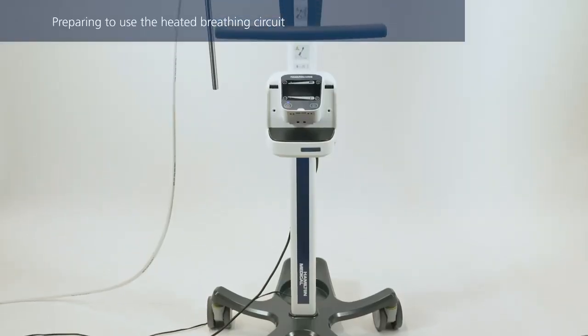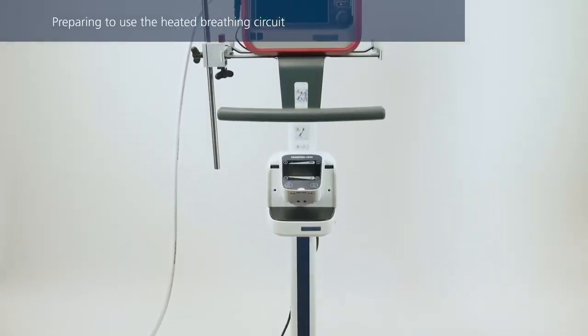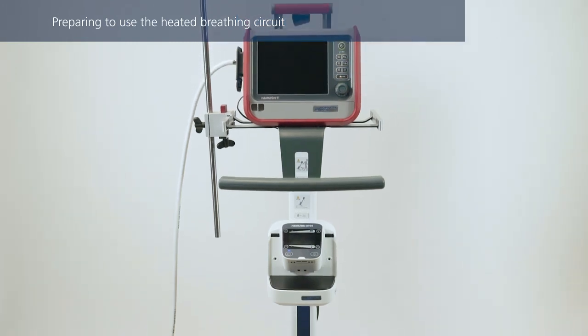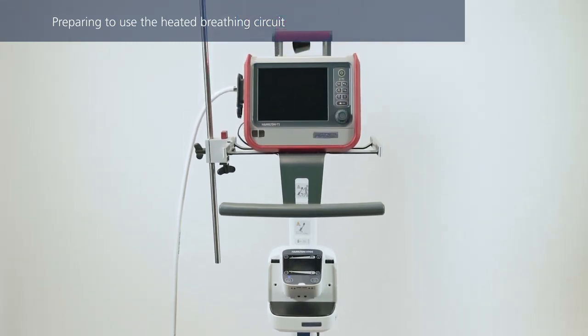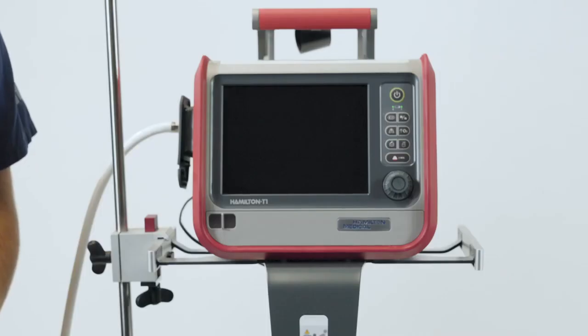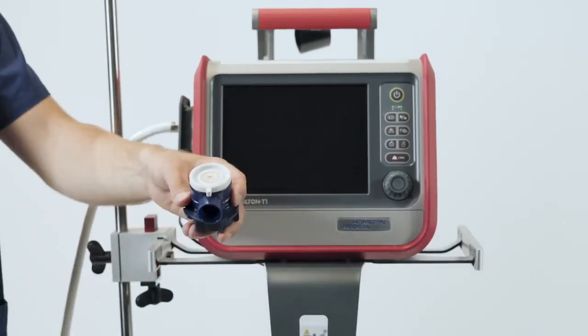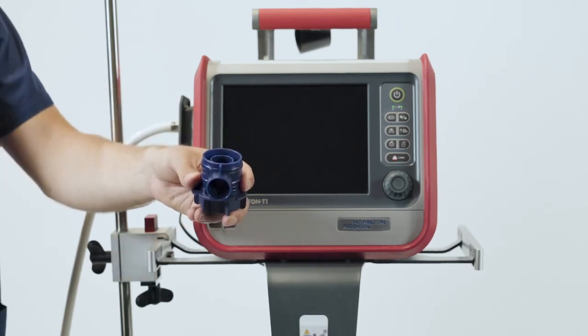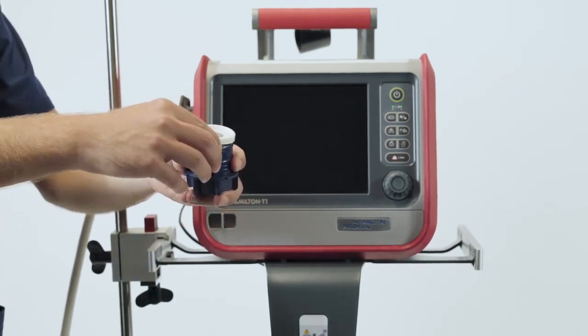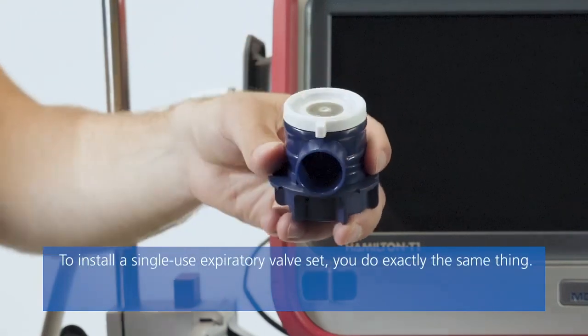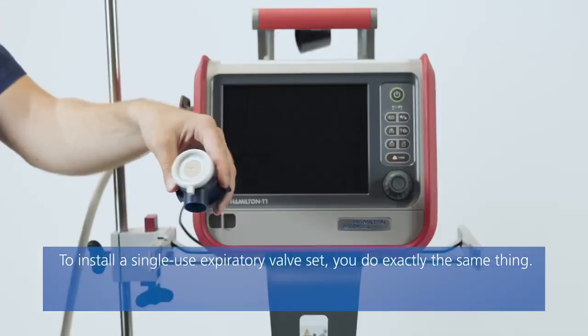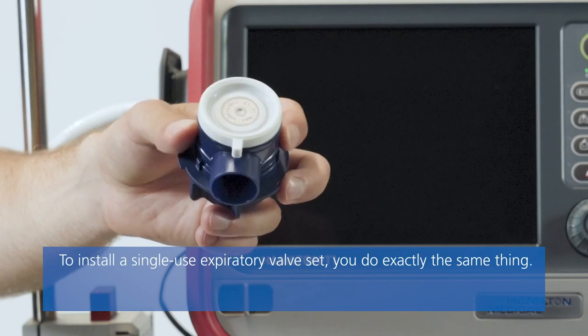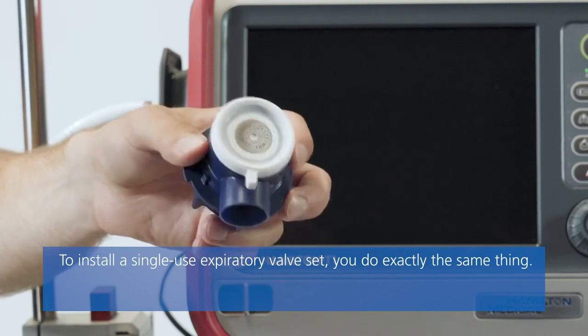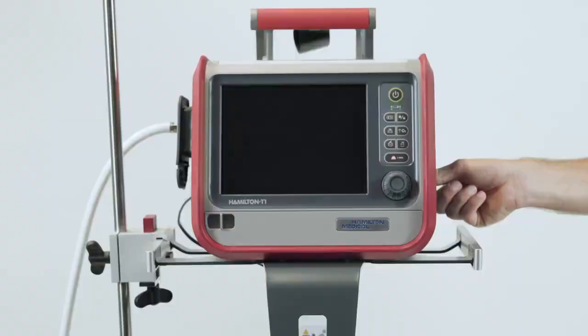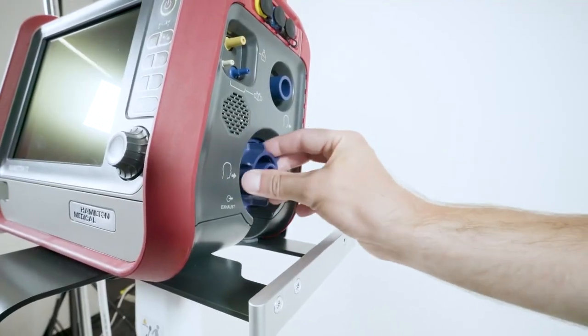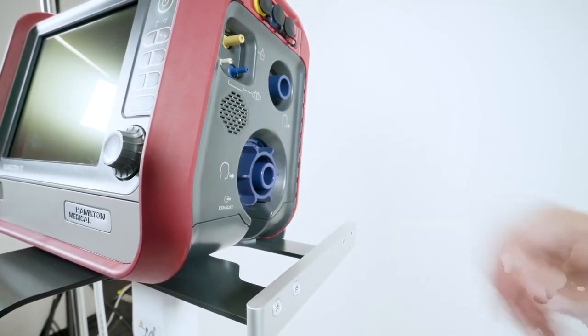If you are using a heated breathing circuit, choose the correct circuit and expiratory valve set according to the patient group or selected treatment. Firstly, install the expiratory valve set. If you are using an autoclavable expiratory valve set, you need to assemble the expiratory valve set first by placing the silicone membrane onto the expiratory valve housing. The metal plate should be facing upwards and be visible. Position the valve in the expiratory port, ensuring it is straight, and twist it clockwise until it locks into place.